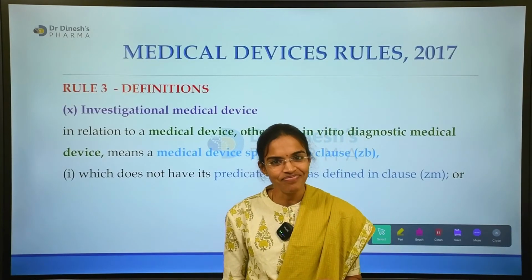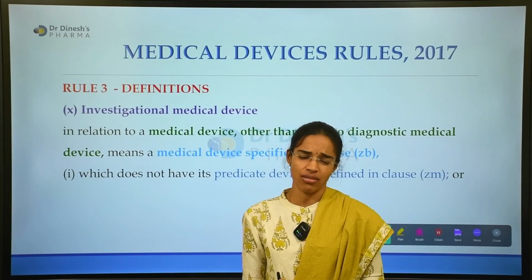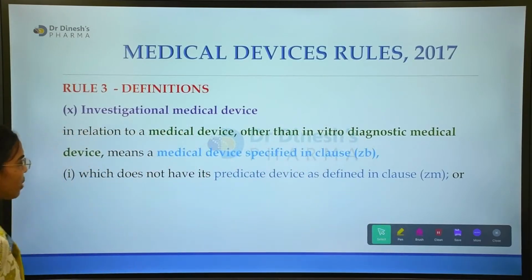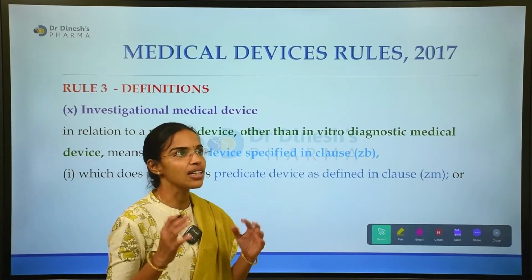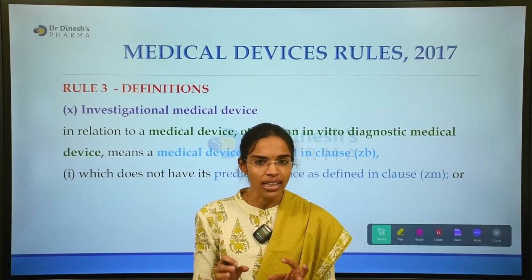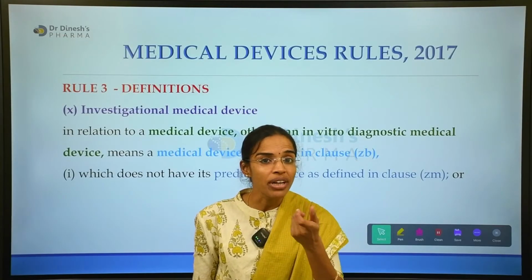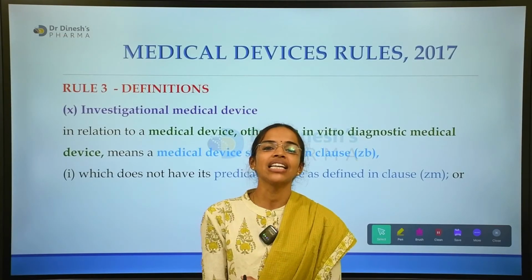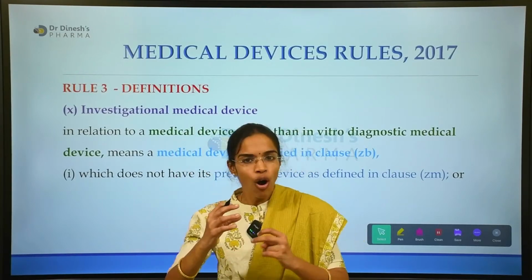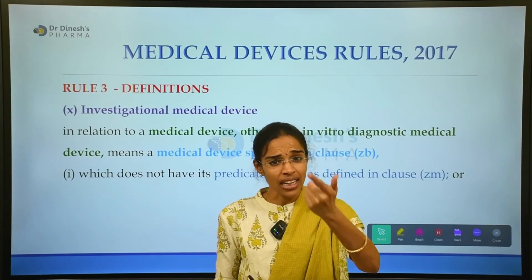Okay, and we move forward. 3X is nothing but the investigational medical device. What exactly is an investigational medical device? There are certain clauses to it. Most probably it is any new medical device on which clinical investigations are to be done, or a medical device which has been modified in such a way that it has to undergo them again.